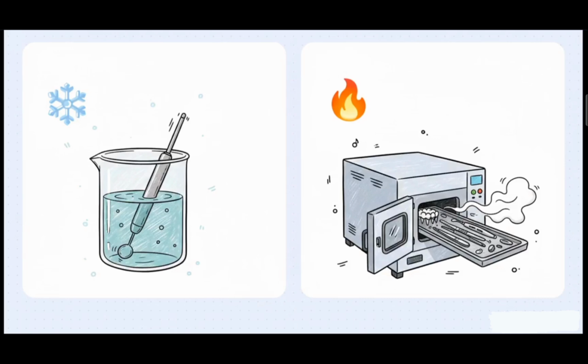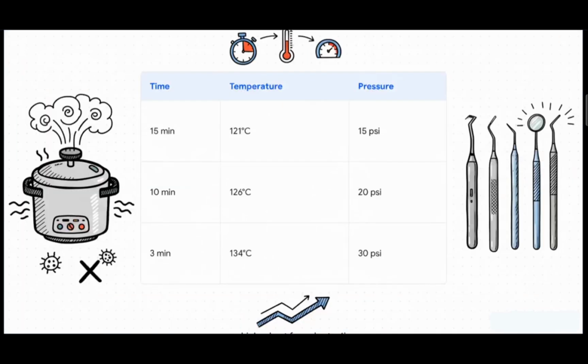The one you see almost everywhere, the industry standard, is heat sterilization, which uses this incredible machine called an autoclave. This right here is where you see the purest science behind the autoclave. Just think of it as a high-tech pressure cooker on steroids. It uses this super precise mix of steam, temperature, and pressure to just annihilate every single microorganism. And look at the table, you can see how it works. At 121 degrees Celsius, it takes 15 minutes. But if you crank up that heat to 134 degrees, boom, you get the same perfect sterilization in only 3 minutes. It's all about controlled, scientific precision.